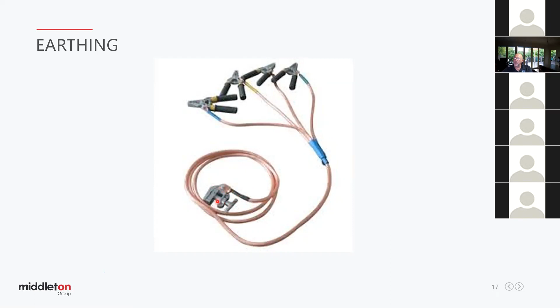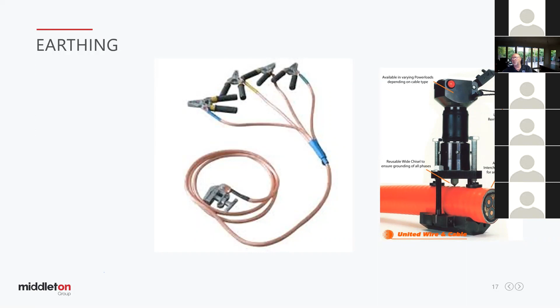Now, when you're playing with cables, you'll use a thing called a cable spike or a spiking tool, which actually punctures the cable and drives an earthed spike into the cable. So if you're breaking out a cable to work on it, you'll apply this spiking equipment and earth the cable to ensure it's dead before you start work. One thing I will say about applying earths, it's really key that you've proved dead. If you apply earths onto a live conductor, it's not a fun experience. But if it's done properly, it should be safe for the operator.